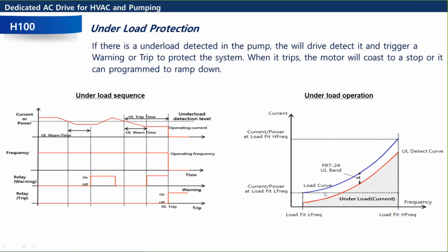You can see on the right here, we have our underload operation. Here's that load curve, which is programmed from that load tune. And then we have a bandwidth. If we ever drop outside of that bandwidth, so if we ever have low amperage, depending on the speed, right? Because we're running variable torque loads here. So the current is going to change based on the speed. That's what a variable torque load is. So if we ever drop to our low current, you have a delay time. If you look over here, there's a warning time, there's a UL trip time.